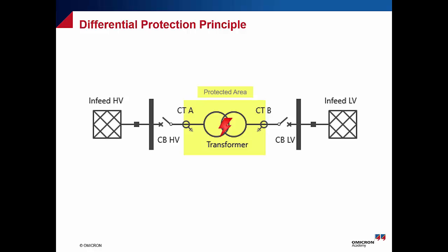For sure, we cannot apply it to small or low voltage power transformers. We have a limit of 5 megavolt ampere and above. If it is less, it is based on the priority of the power transformer whether to apply differential protection, because it is costly and we have to make sure that this cost is not expensive compared to the price of the asset itself.